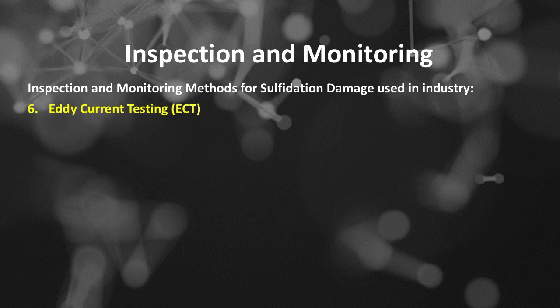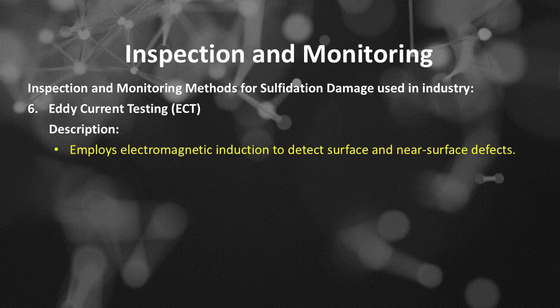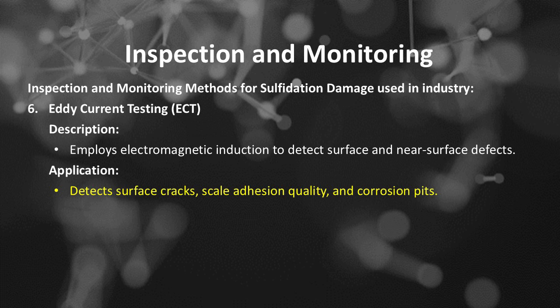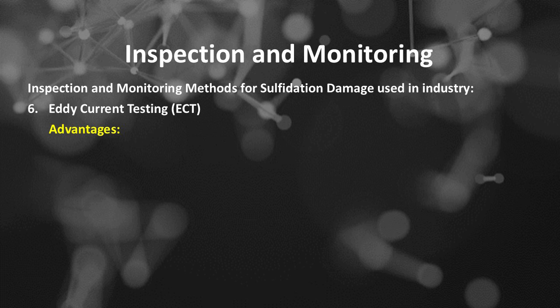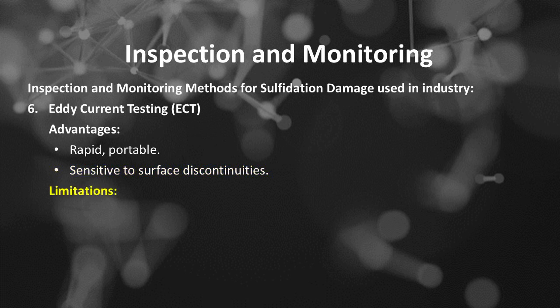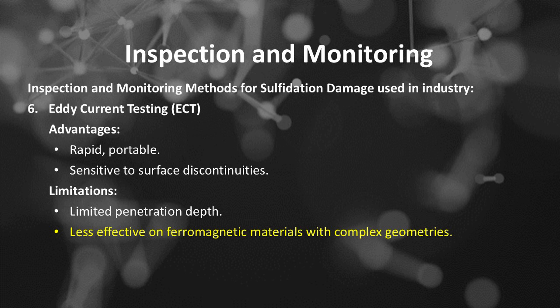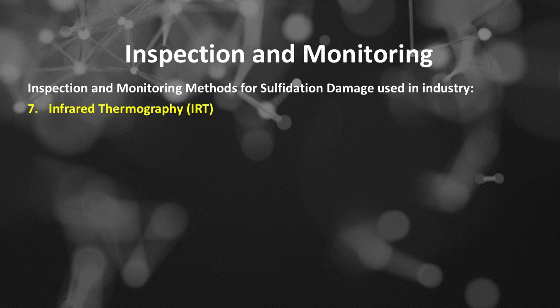Number 6 is eddy current testing, or ECT. Description: employs electromagnetic induction to detect surface and near-surface defects. Application: detects surface cracks, scale adhesion quality, and corrosion pits. Advantages: rapid, portable, and sensitive to surface discontinuities. Limitations: limited penetration depth, and less effective on ferromagnetic materials with complex geometries. Number 7 is infrared thermography, or IRT.